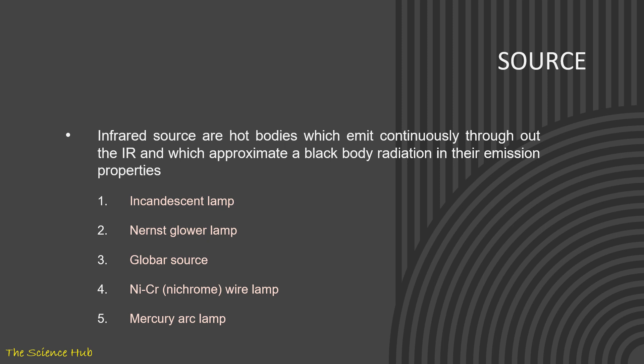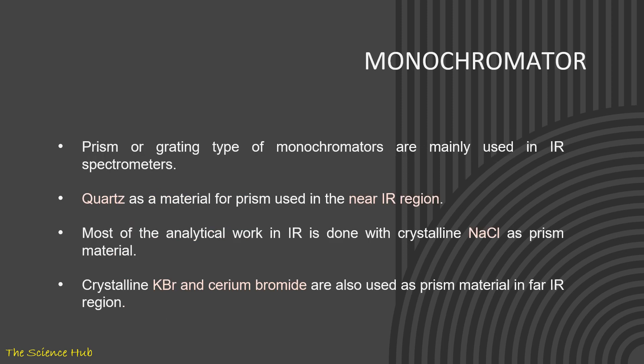First we're talking about source. Infrared sources are hot bodies which emit continuously throughout the IR and which approximate a blackbody radiation in their emission properties. What are the sources used in IR spectroscopy? That is incandescent lamp, Nernst glower lamp, globar source, nichrome wire lamp, mercury arc lamp. Next is monochromator. Prism or grating type of monochromators are mainly used in IR spectrometers. Quartz as a material for prism is used in near IR region. Most of the analytical work in IR is done with crystalline NaCl as a prism material. Crystalline KBr and cesium bromide are also used as prism material for far IR region.